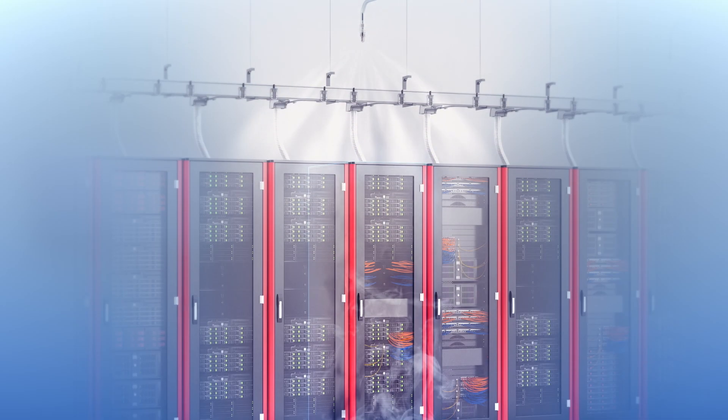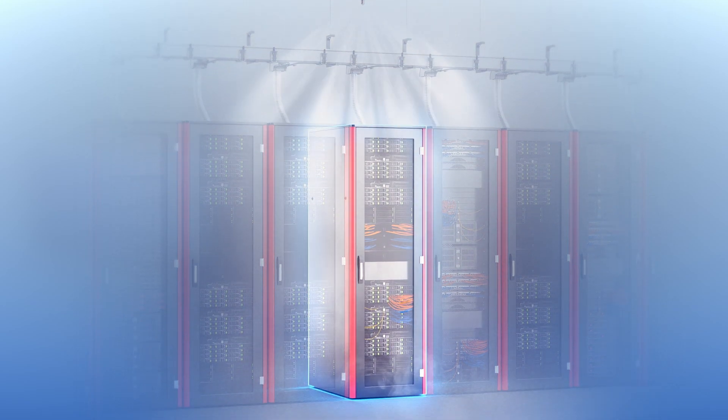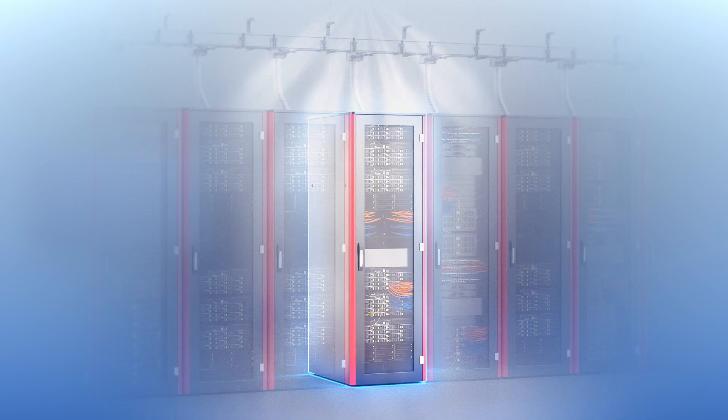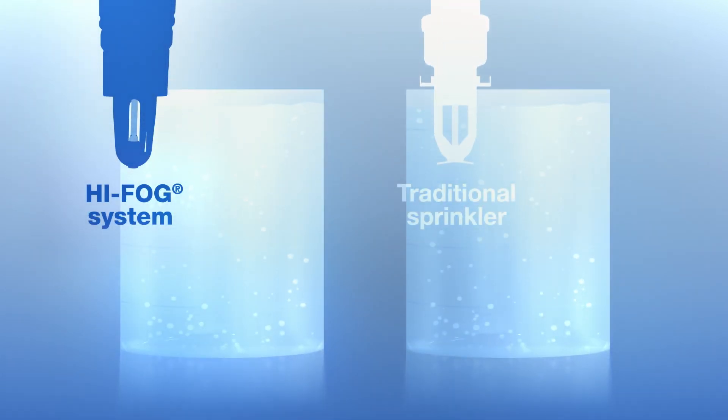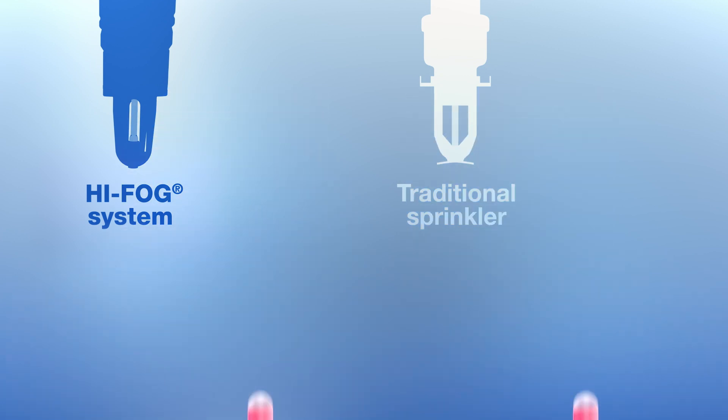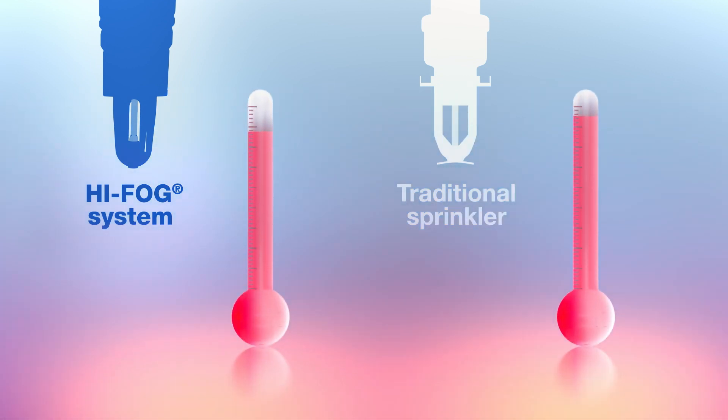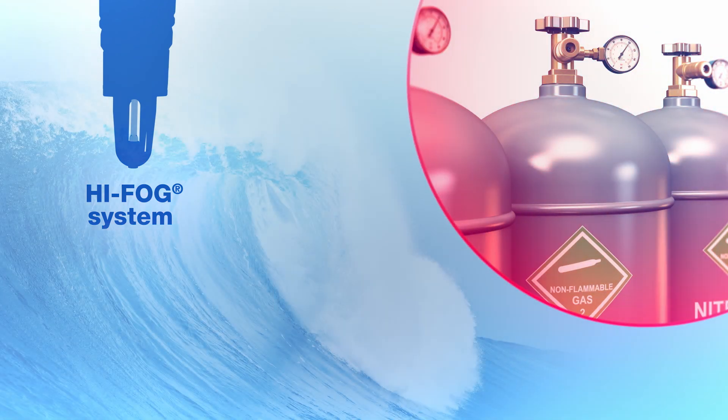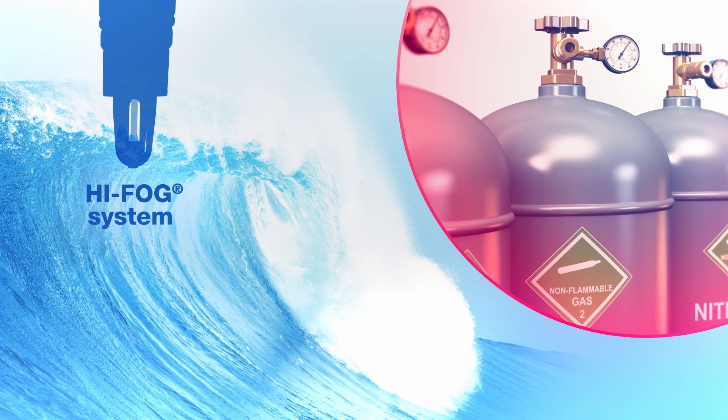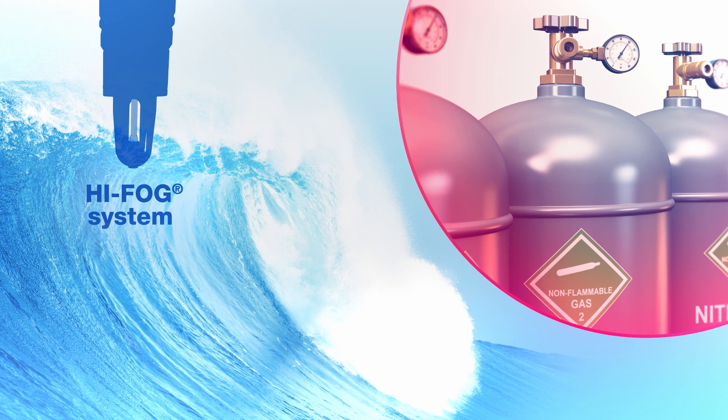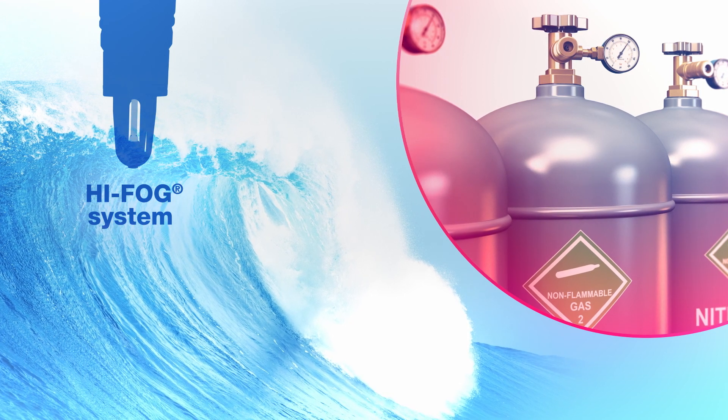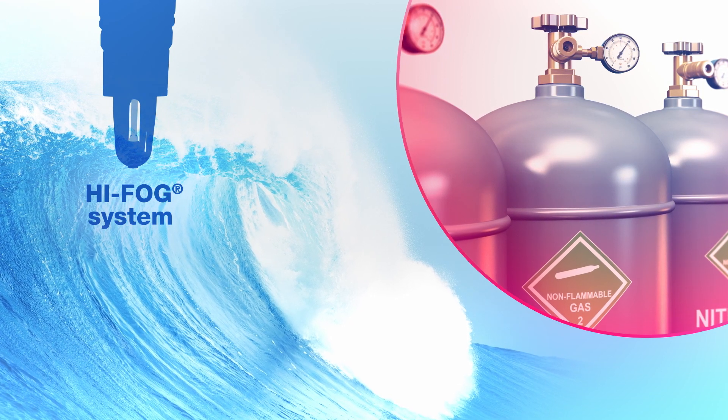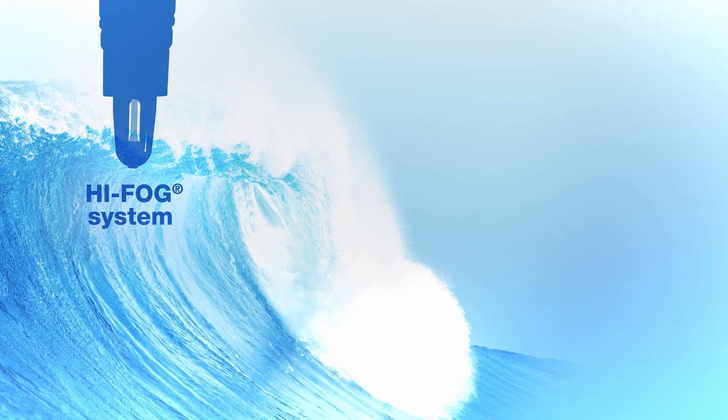Water is discharged only to the area of fire, not to the entire data hall, subsequently preventing flooding at the premises. HIFOG uses significantly less water compared to traditional sprinkler systems. Cooling is also more efficient in comparison to traditional sprinklers or low-pressure water mist systems. Unlike expensive gases, water is a commodity with no risk of being banned by authorities. Using water mist is not restricted to one shot of operation either.